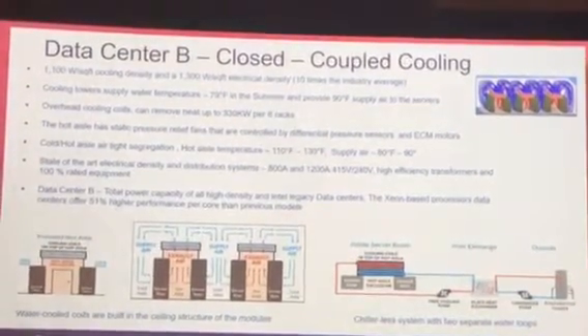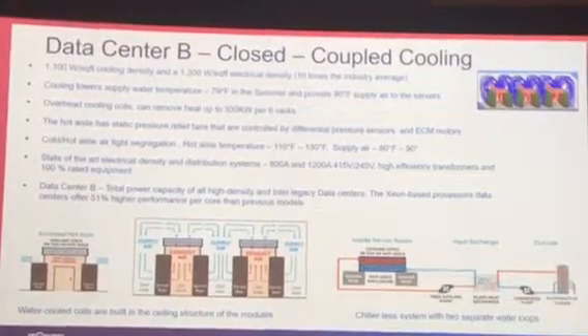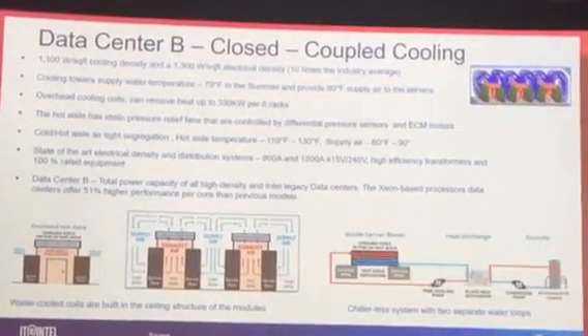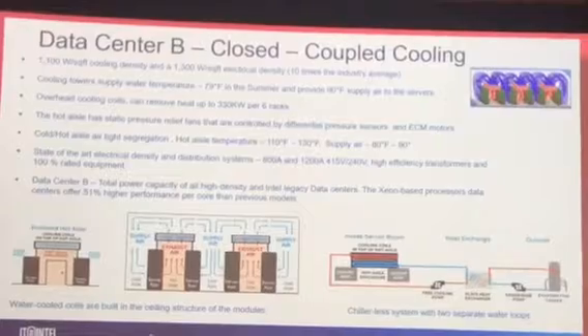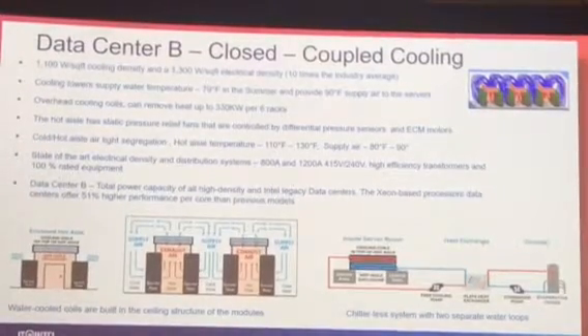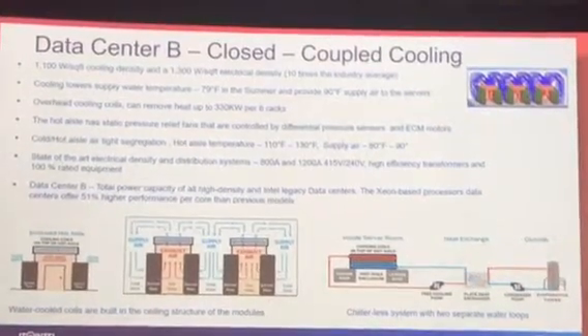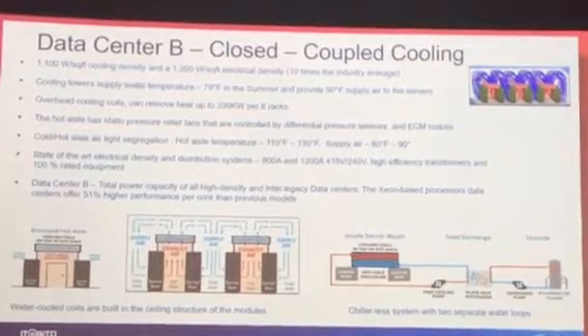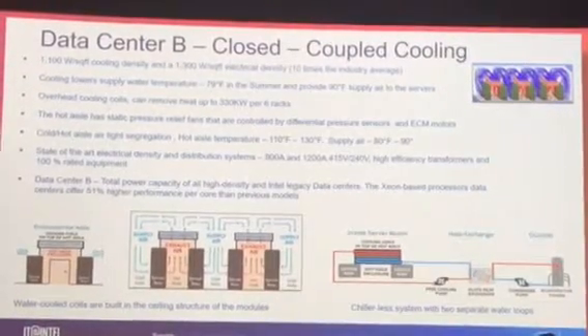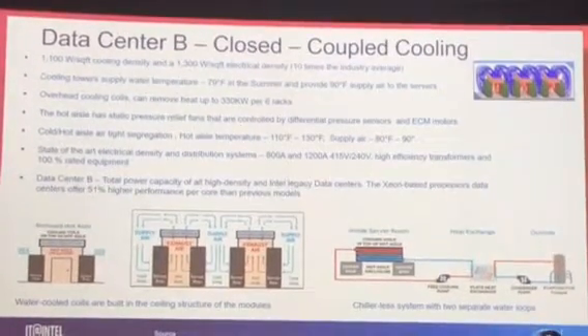You can see the temperature that we operate in between 110 Fahrenheit to 130 Fahrenheit in the hot aisle, and the supply air between 80 to 90. With the cooling tower, we don't need chillers in the Bay Area because, again, the wet bulb temperature works fine, so we don't need the chillers over there.